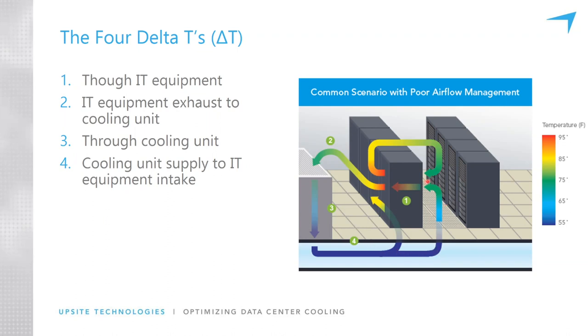You can put all the containment in the world, and this is one of the most misunderstood concepts in the industry, is that you can put all the containment in you want and you are not going to reduce delta T2 unless you reduce fan speeds through cooling units. There is no way to stop that extra conditioned air. If there are only 4 units of air moving through all the IT equipment, but you've got 20, 30 units of air moving through all your cooling units, that extra air is going to find its way somehow back to the cooling unit. It has to. And it's going to end up mixing and reducing that temperature. So you put containment in place, then you can reduce fan speeds and optimize the room.